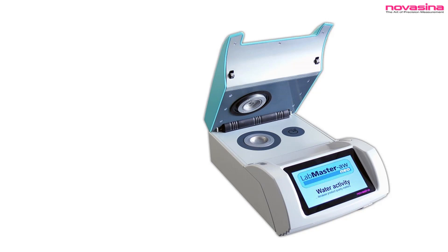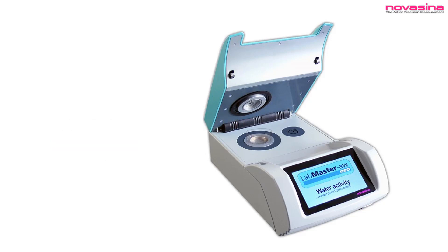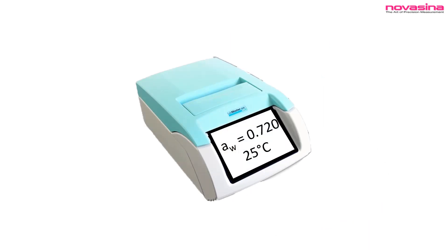So you have a water activity instrument, or maybe you're thinking about getting one. The test seems pretty simple: you place a sample in the instrument, push the read button, the test runs, and a water activity value appears on the screen. The water activity reported is 0.720 at 25°C.